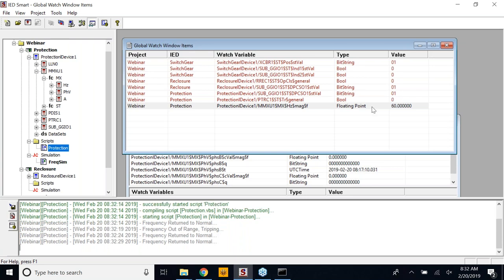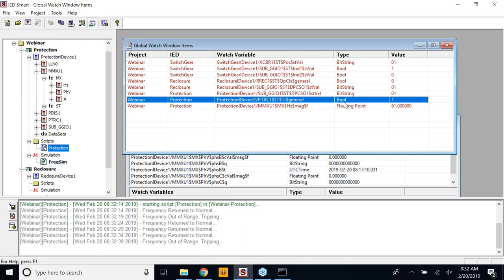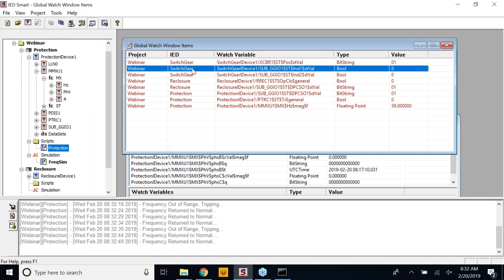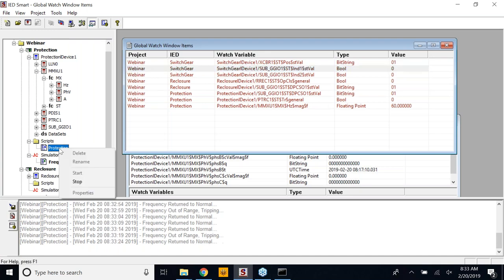This is the switchgear device — it is subscribing for the PTRC trip conditioning signal. As the signal changes under the PTRC, it is getting reflected in the subscriber device also. As we run these scripts, we could also generate manual data simulation. Right now, to avoid further data changes, I will stop the script so that we could manually change some data and see the results. What we were seeing was a trip signal going out to the switchgear.